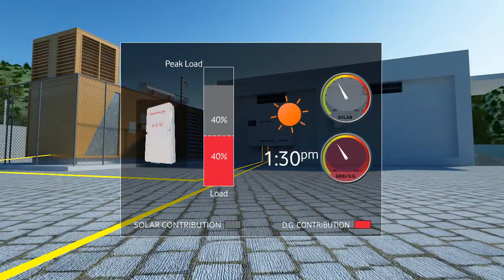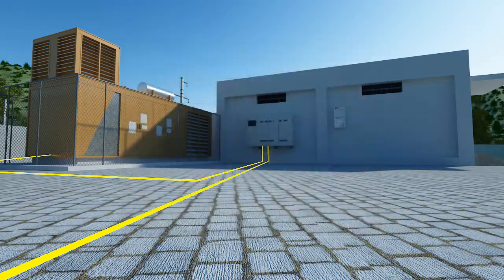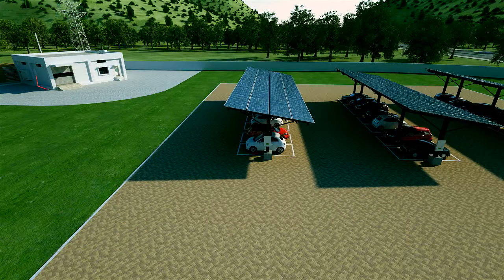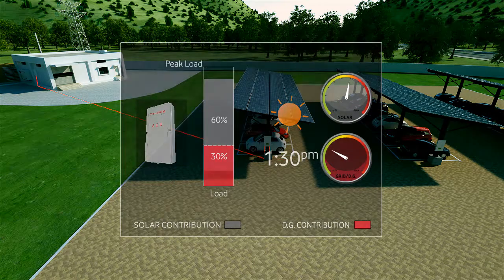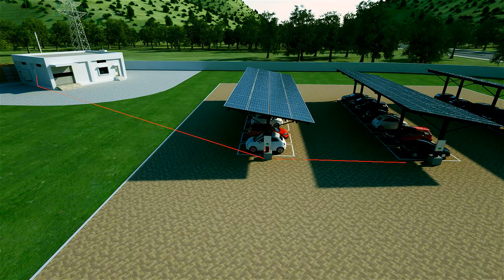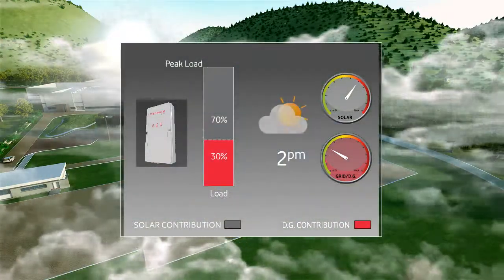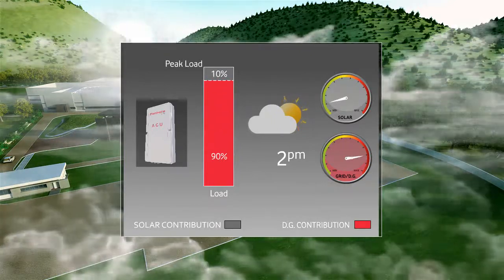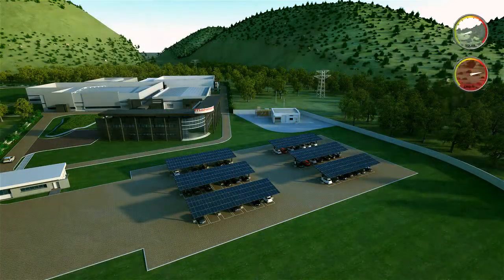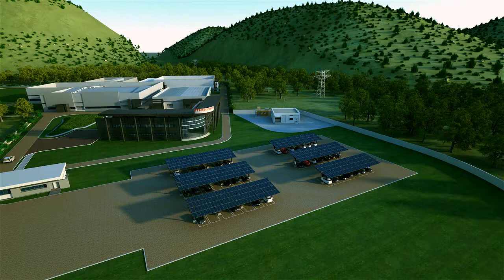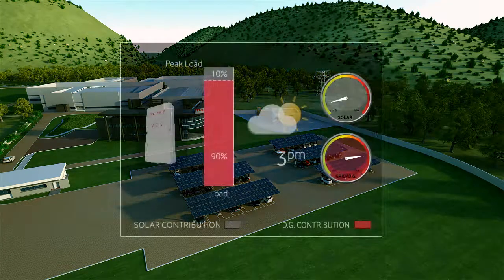As load increases, the power drawn from the diesel generators increases. MAX senses the load rise, brings back solar inverters to their peak capacity and reduces power drawn from the diesel generators. A sudden cloud can lead to a drastic drop in solar generation. In that case, power is met from the diesel generator. As the cloud clears, solar increases automatically.